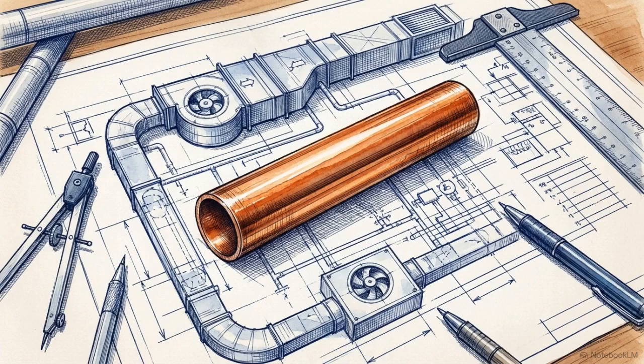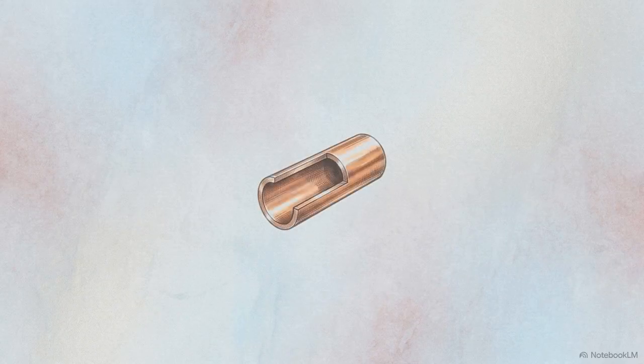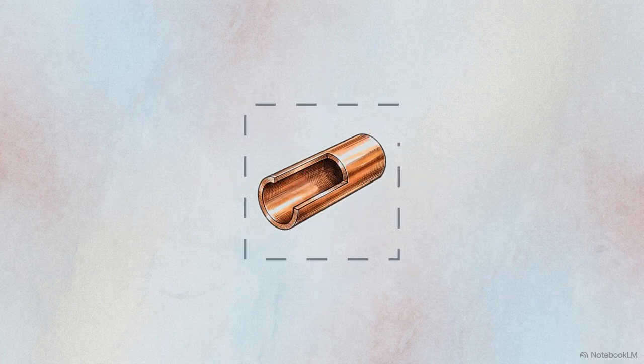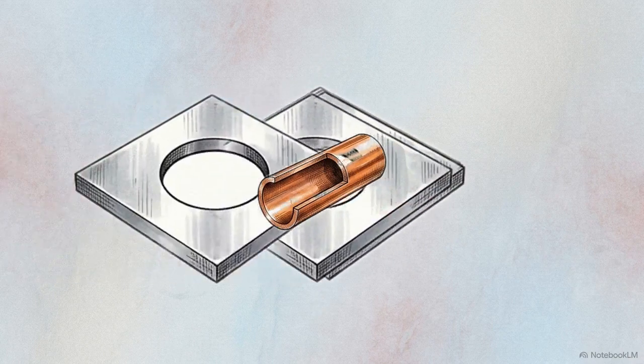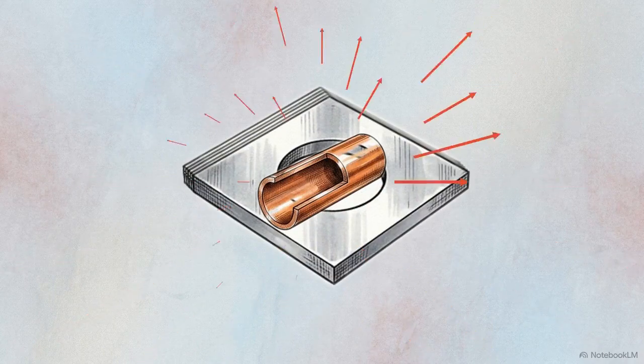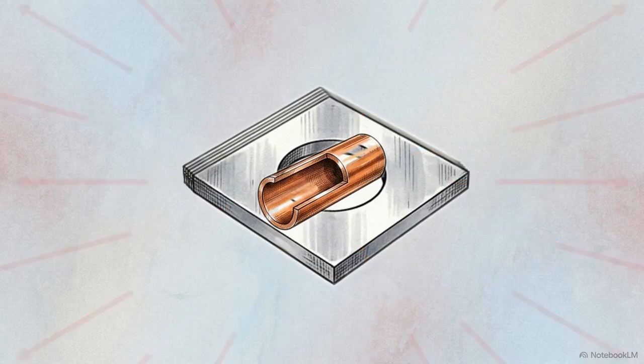To translate this strict thermodynamic rule into physical engineering, we have to look at how we accelerate that heat transfer in the real world. This 3D cross-section shows the primary material choice: copper tubing. Copper is selected for its supreme thermal conductivity, allowing heat to rapidly radiate outward from the refrigerant, while possessing the tensile strength to withstand high internal pressure. But a bare copper tube faces a severe geometric limitation. It simply lacks the total surface area required to dump heat into the surrounding air fast enough to sustain the cooling cycle. The solution is to press tightly bonded aluminum fins over the copper.